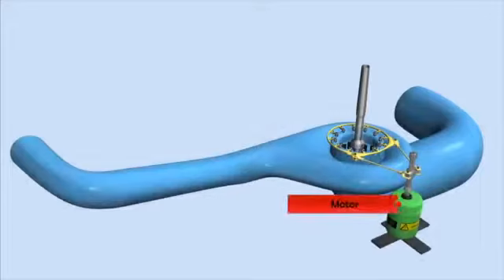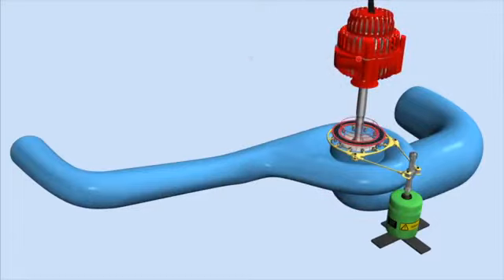The runner of a Kaplan turbine looks like a propeller or the screw of a ship. Adjustable pitch vanes enable it to work efficiently over a range of flow rates. The pitch vanes are driven via an electric motor. At one end of the turbine axle, a generator produces electricity when the runner is turning.